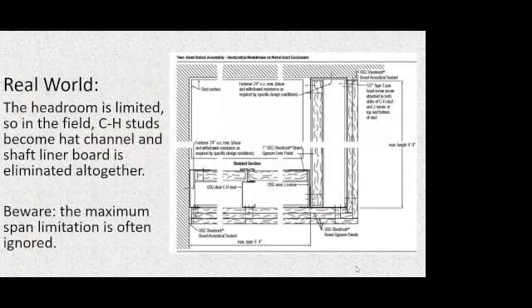The span limit is 5 feet 4 inches internal dimension, and the depth is 48 inches inclusive of the assembly itself. So that in reality results in a maximum duct dimension once you account for a hanging system to hold it up and the little bit of room that takes. The drywall solution caps out, if it has a 2-hour wall, for continuity support on one side at a maximum duct depth of about 36 inches and a maximum duct width of about 60 inches. If the duct's bigger than that, drywall is not an option with just one wall.